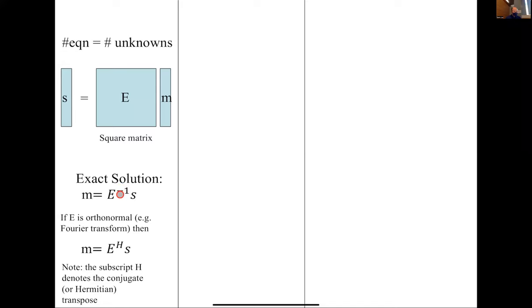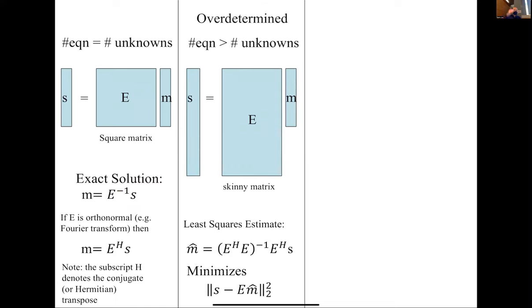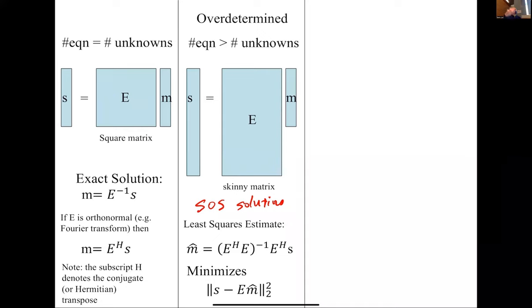The next thing is: what happens if we have more coils — many coils imaging at the same time? That's known as parallel imaging. In that case, we'd have more equations than unknowns, which is called an overdetermined problem. We have a least squares estimate, giving us the sum-of-squares solution. You take every coil, square it, add those squares, and take the square root. That's a pretty good estimation, and it can still be seen on scanners when you have multiple coils running a standard sequence.